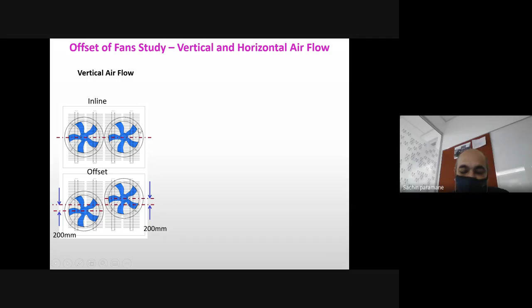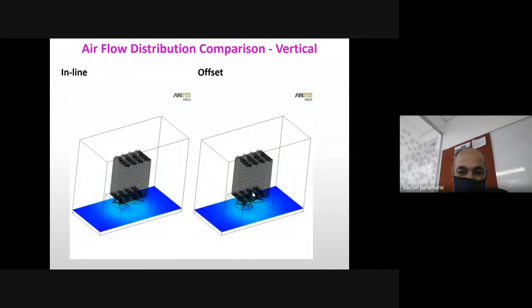So this is airflow distribution comparison when the fans are blowing air in a vertical direction. Left is inline and right is offset. So here also we can see that there is a sideways escape of the air when the fans are blowing the air in a vertical direction, and when we offset these fans, then there is a significant improvement in the airflow distribution over the radiators, which will improve the heat dissipation from the radiator.